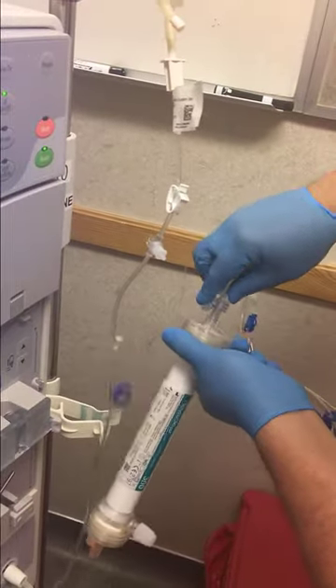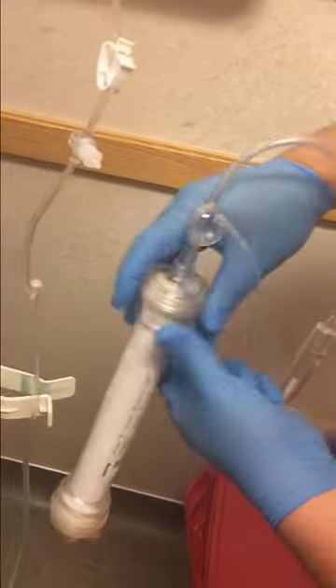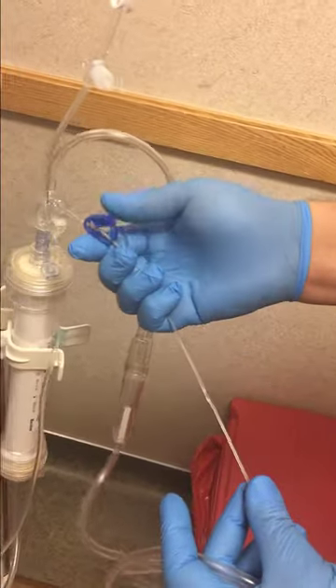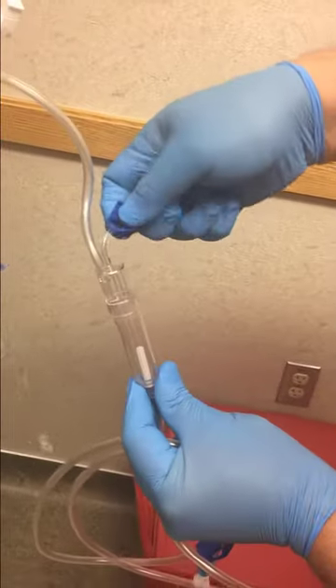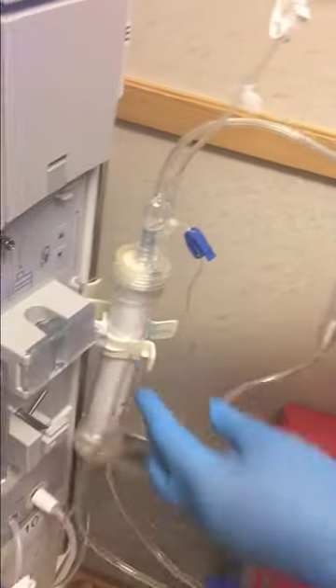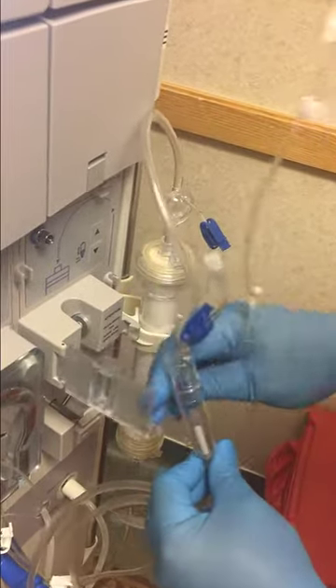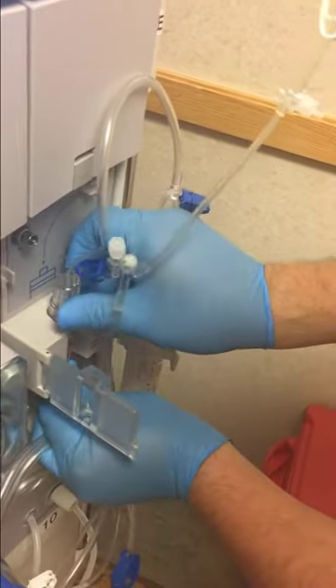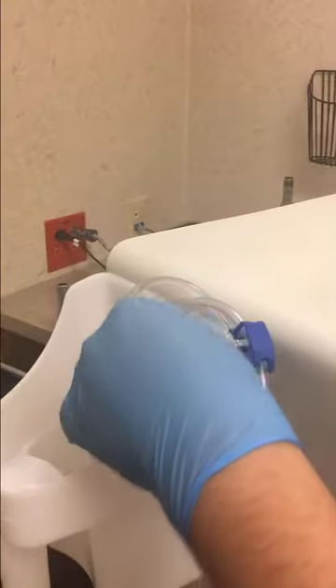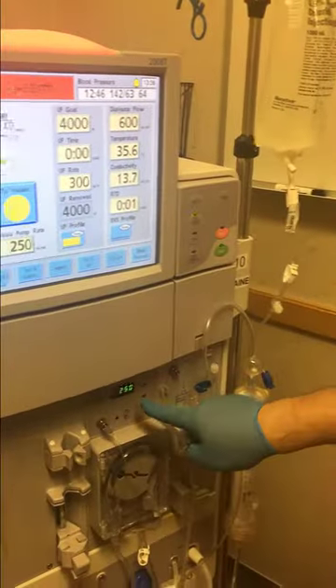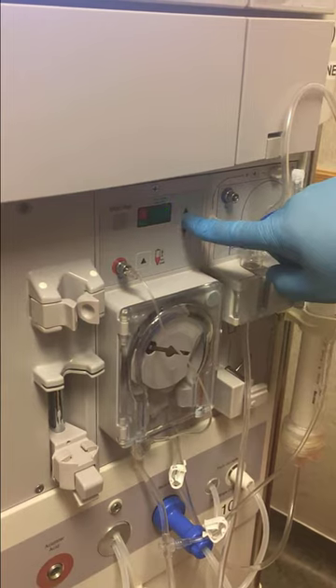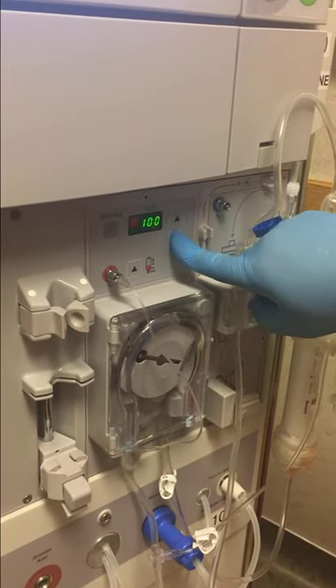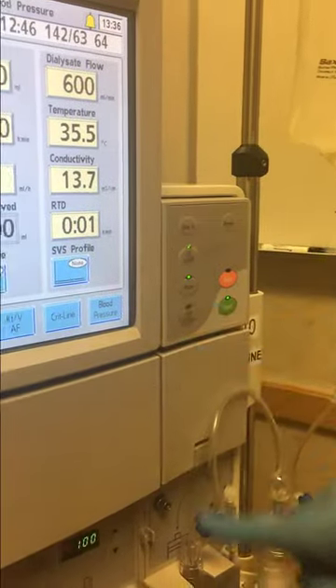And now you're going to attach your venous tubing. And place your venous trap into the holder. And shut the door. And place your patient line, your venous patient line, into the saline bucket. Now you need to turn the pump speed down to 100. And select your prime button on the machine.